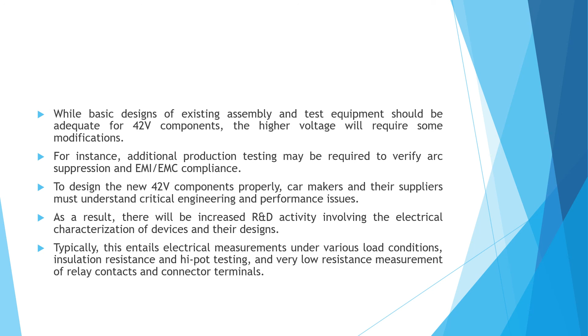To design the new 42-volt components properly, car makers and their suppliers must understand the critical engineering and performance issues. As a result, there will be increased R&D activity involving the electrical characterization of devices and their designs. Typically, this entails electrical measurements under various load conditions, insulation resistance and high pot testing, and very low resistance measurement of relay contacts and connector terminals.